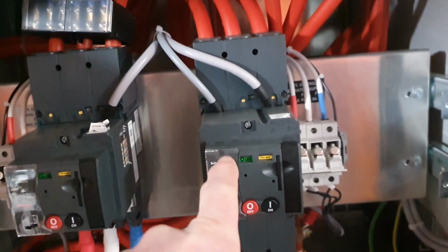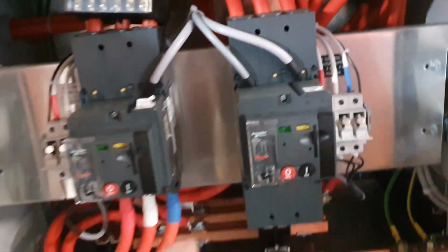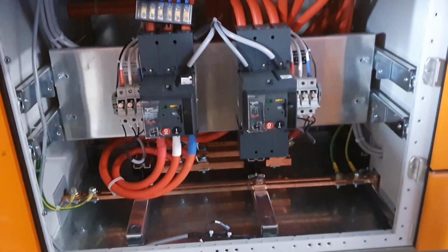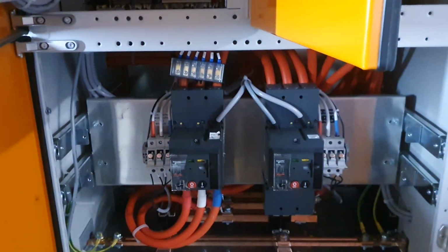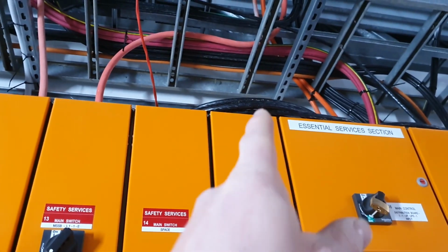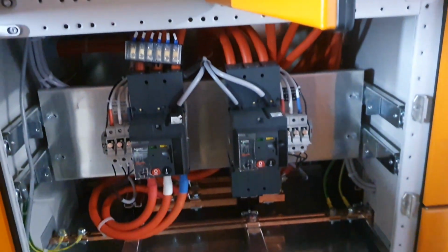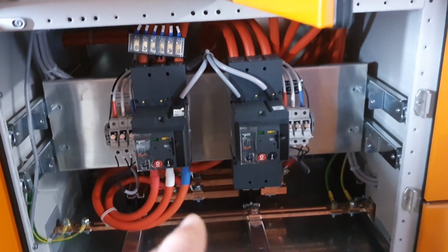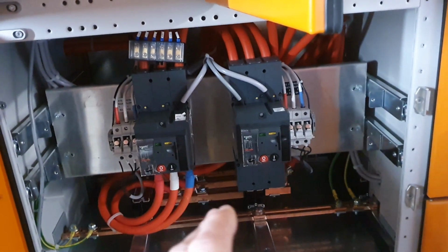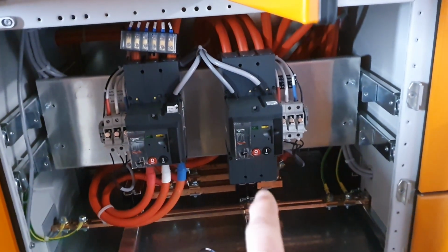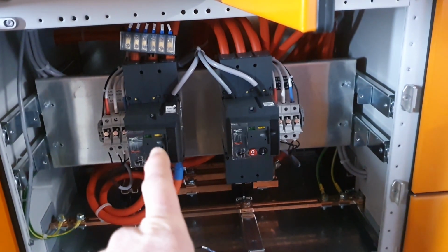Alright, so what this does is if there's a blackout, the control here will detect it and send a signal to the generator through one of the control cables we've got - I haven't terminated it yet, but that's it there. So it'll send a signal to the generator to start. When it gets that signal back saying the generator is running, this switch will turn off and then this switch will turn on.